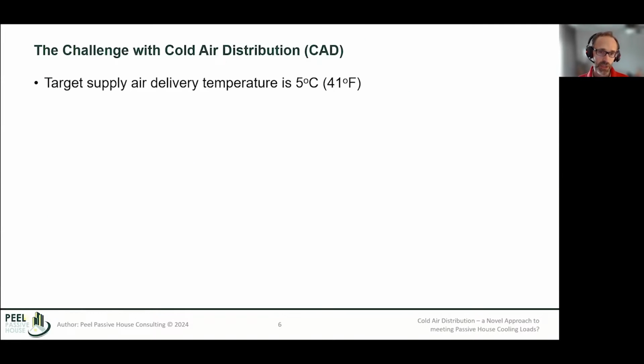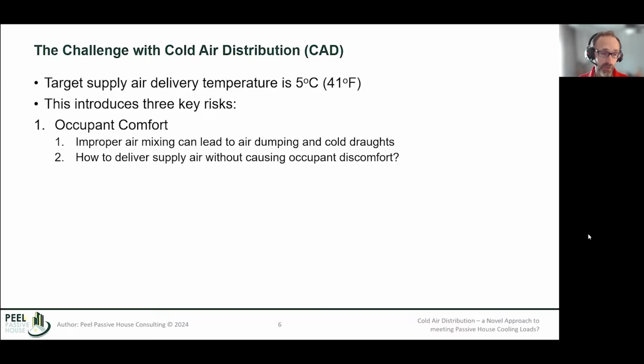Okay. Now, the challenge with cold air distribution is the supply delivery temperature, right? So we're targeting a 41 degrees Fahrenheit supply temperature coming into the room, where you can imagine, that might be a challenging thing to do. And indeed, there are three key risks that this introduces. First is occupant comfort. So, if we're not getting good air mixing, we could get some air dumping, cold drafts. So how do we deliver the supply air into the room without causing occupant discomfort?